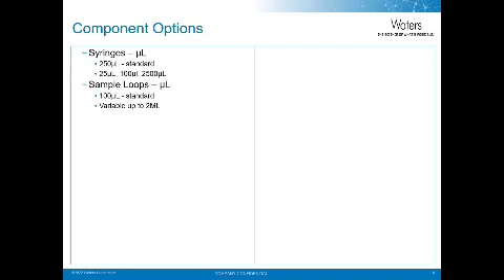Other component options include syringes. So the standard syringe is 250 microliters. Other syringes that can be purchased can be 25 microliters, 100 microliters, or 2500 microliters. Also an option is different sample loop sizes. The standard sample loop size is 100 microliters. These are available in variable sizes up to 2 milliliters. The weight of the system is 130 pounds. The total system volume is less than 650 microliters.